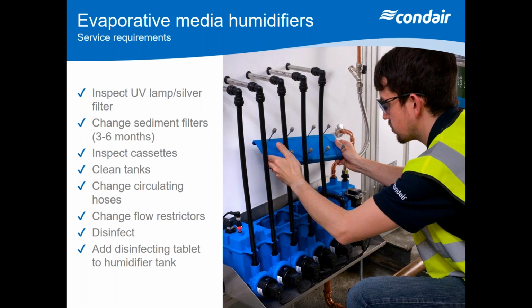One of the most important things to consider is flow. The cassettes are designed to give you a certain capacity, but also what we call washover. So we wash the cassettes over to make sure we're pushing the scale through the system and into the tank. So it's very important to change flow restrictors to make sure they're giving you the correct flow. And if you're using pumps, it's also important to correctly set those pumps on a regular basis. Because if you don't get the correct flows over the cassette, then you're going to get inconsistent evaporation, and also you're going to get more scaling. So it's very important to make sure you get the restrictions and the settings right.